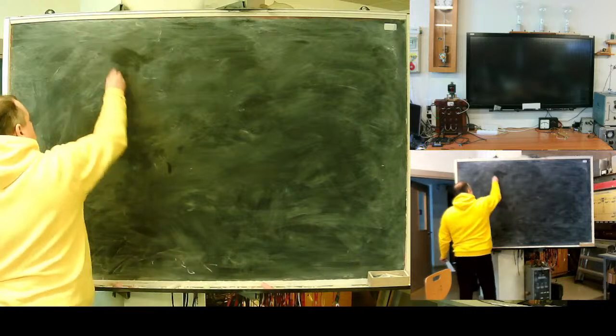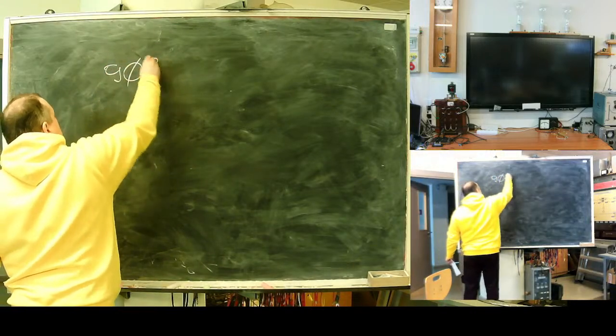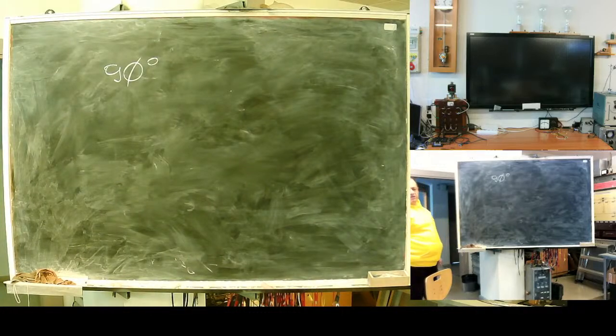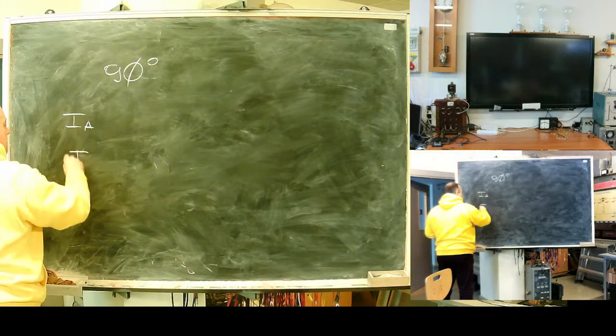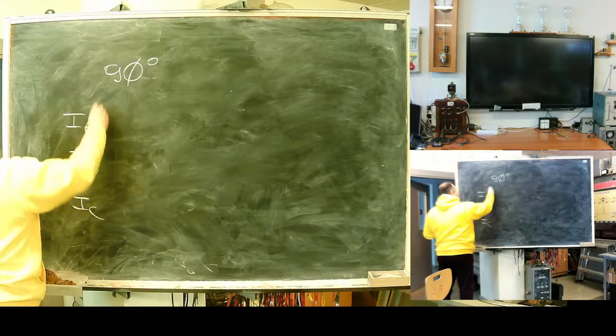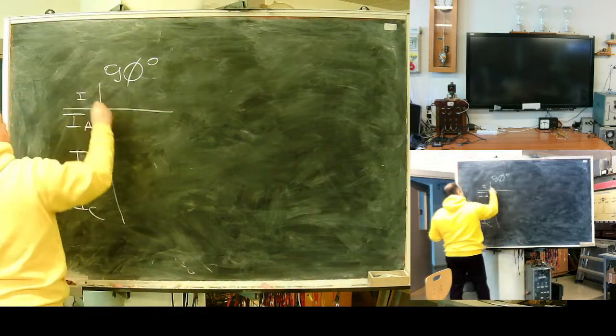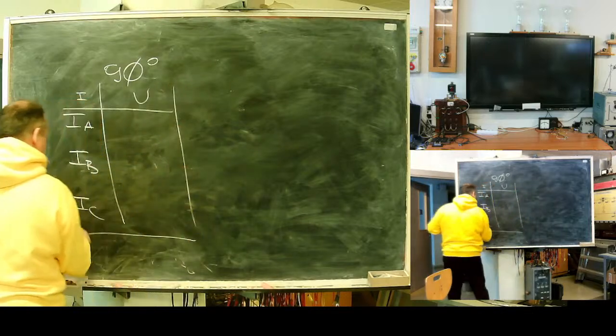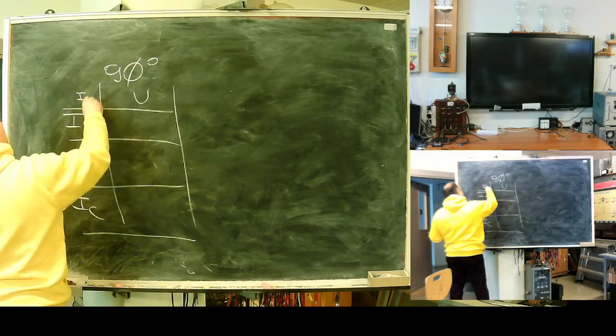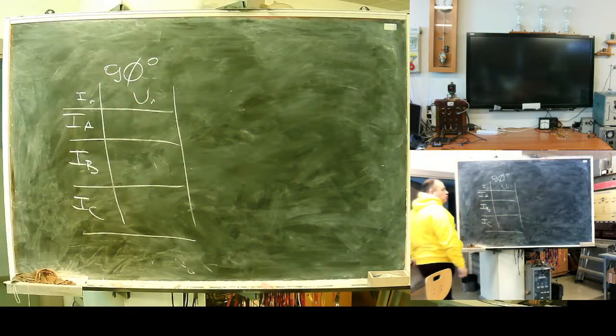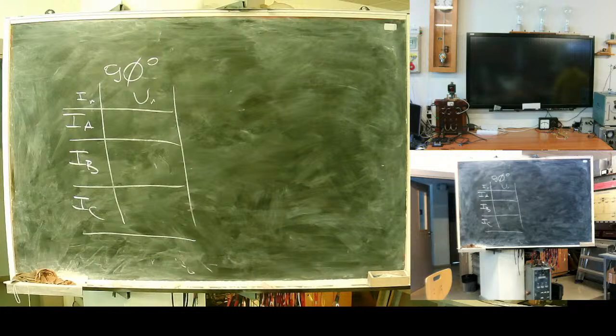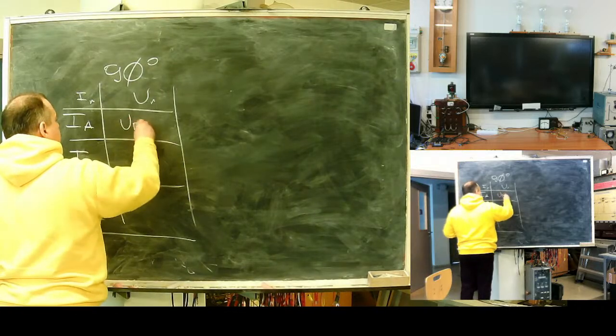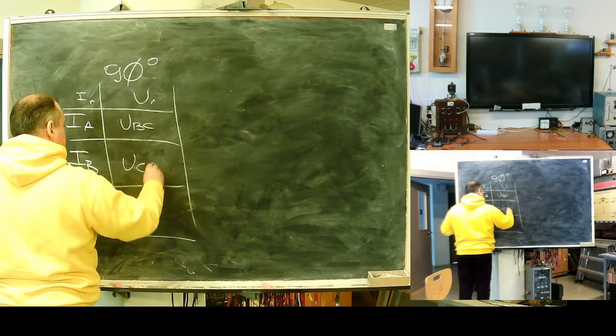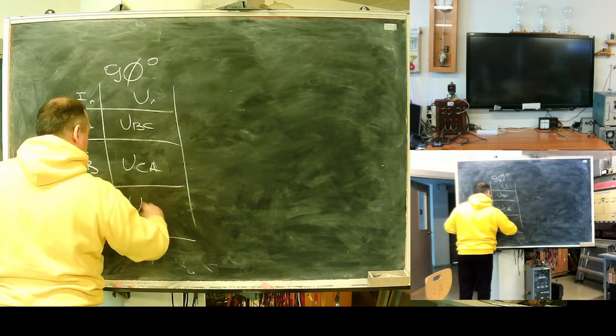So, the basic standard, the so-called 90 degrees connection schematics. In 90 degrees connection schematics, currents are A, B, C. Current, voltage, voltage for the relay, the so-called polarizing voltage. What voltage should be taken into account? BC, CA, and AB.